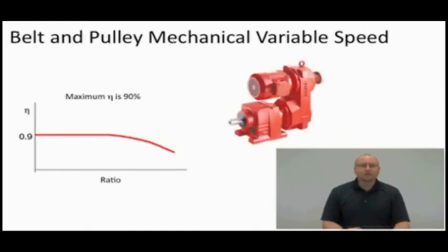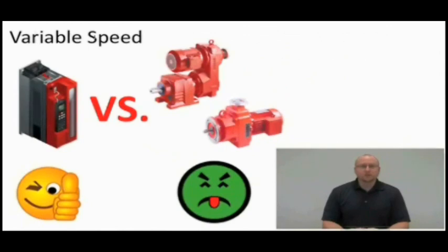Same thing with a belt and a pulley. It has a similar operating curve, where as the ratio goes up, your efficiency goes down. So they're not very efficient. An inverter is going to be a little bit more efficient than, well, not a little bit, a lot more efficient than a mechanical variable speed device.